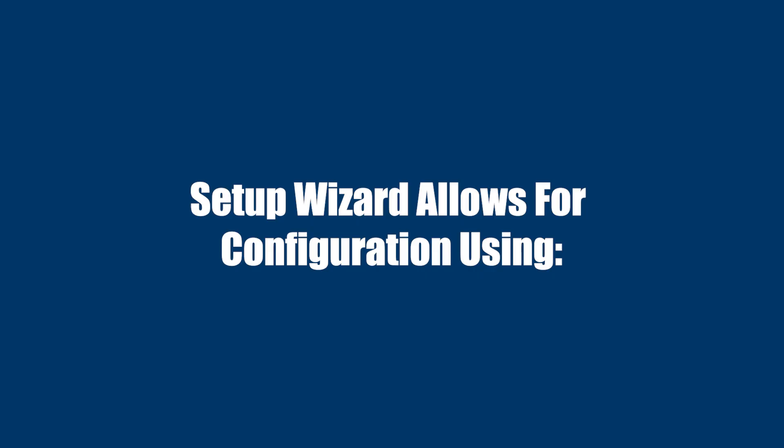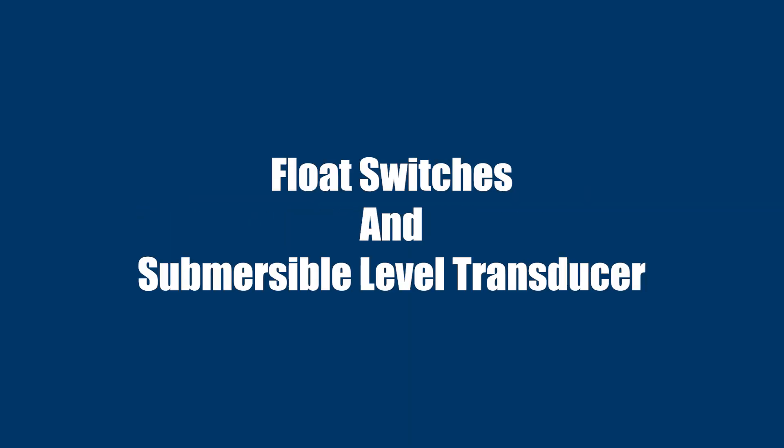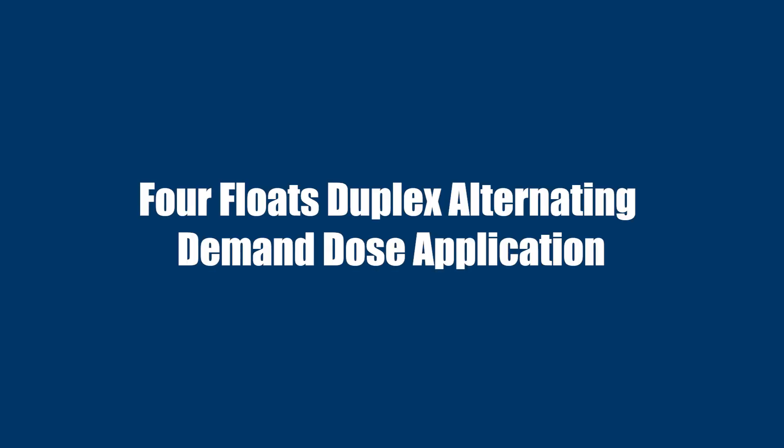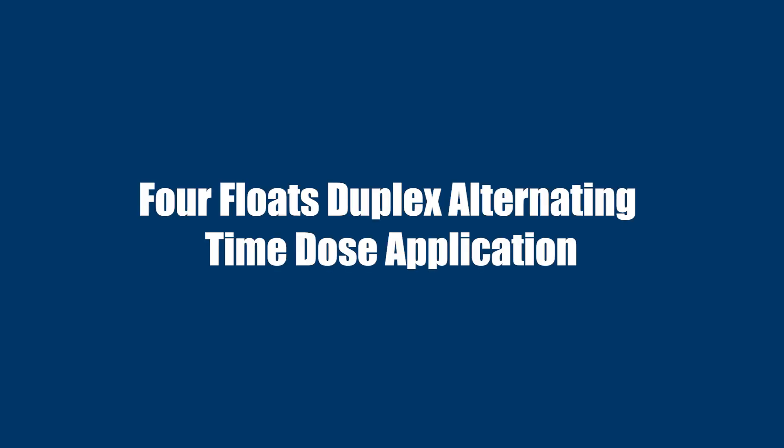Please note the setup wizard allows for configuration using either float switches, a submersible level transducer, or both floats and submersible level transducer. We will first demonstrate a four-float system for a duplex alternating demand dose application. Second, we will demonstrate a four-float duplex alternating time dose application.